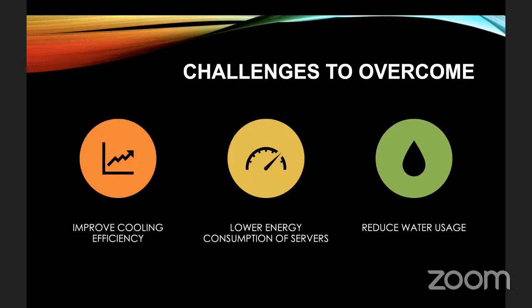So in order to meet the future needs and the world's hunger for technology, but also remain sustainable, there are challenges that must be overcome. Improving the cooling efficiency, lowering the energy consumption of the servers, and reducing water usage could be highlighted as the three main aspects. And as you will see, a lot of these are interconnected. If you can improve cooling efficiency, you can reduce water consumption. If you can lower the energy consumption of the servers, you lower the cooling requirements, which also lowers the amount of water required, not only to power them through the generation of electricity, but the water used to cool them. So if you can improve one of these, it will improve all of them.